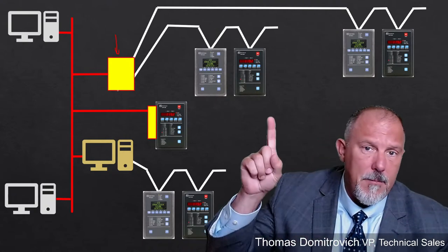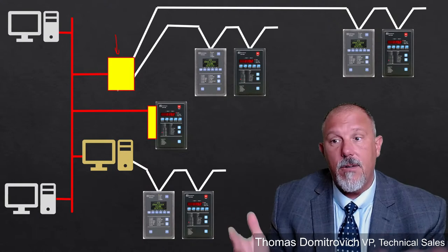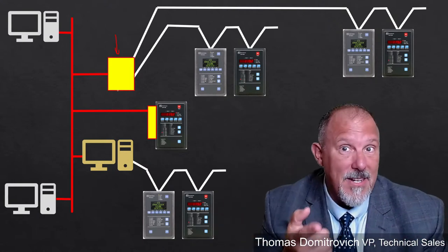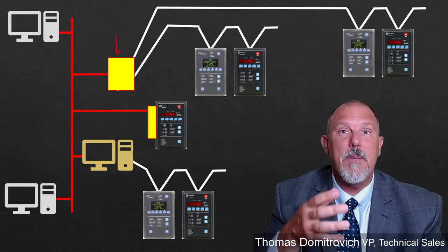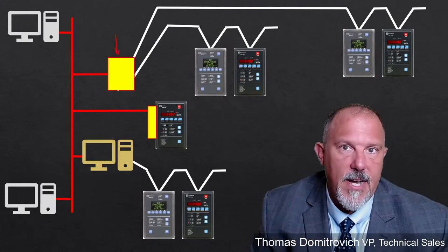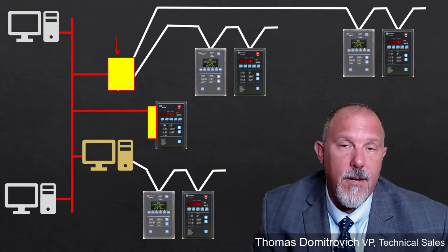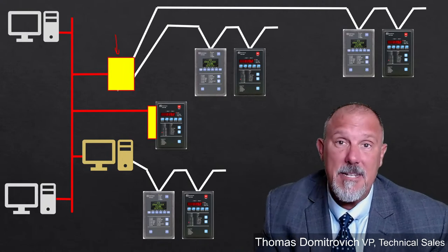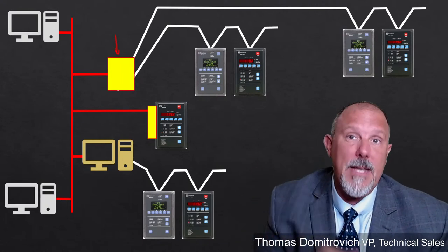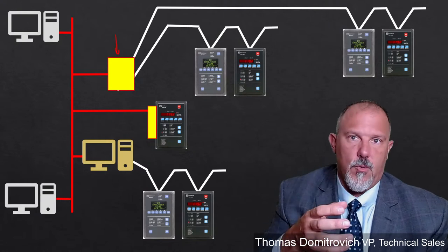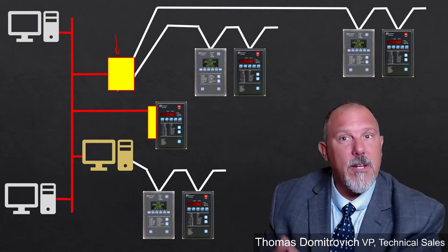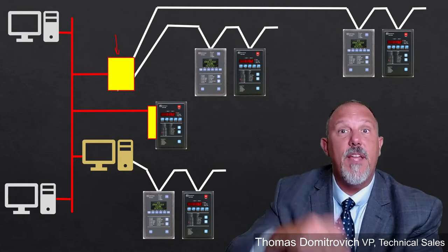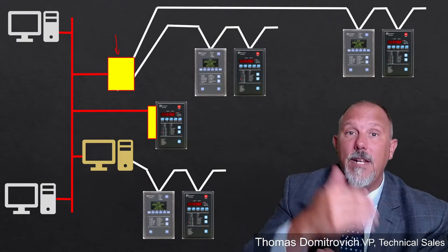You may say, I bought the meter, but you found out that, oh my goodness, I need to buy a communication module that mounts on the back, dependent upon the protocol. There may be a communication module for RS-485, a communication module for Modbus RTU, another communication module for Modbus TCP or Ethernet or TCP/IP. There might be different modules depending upon the protocol for the network that you plan to place it on. So you're going to want to talk to the manufacturer and make sure it is clear on what you're trying to get it into.